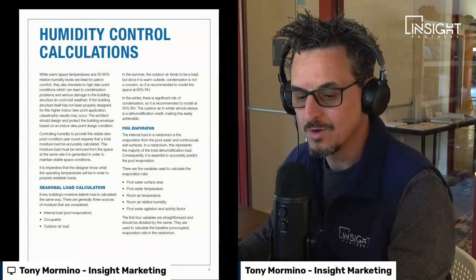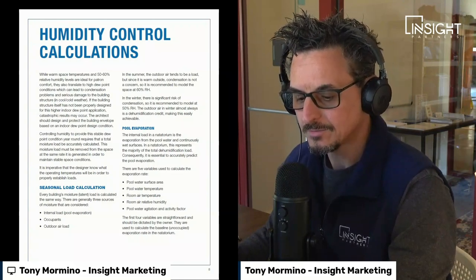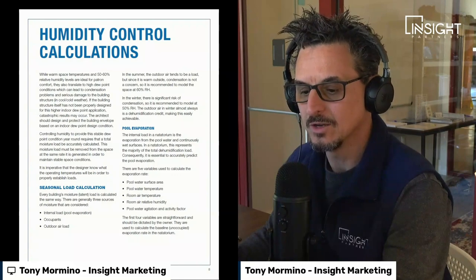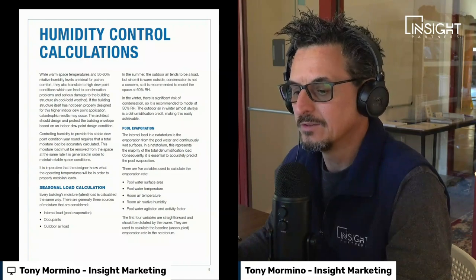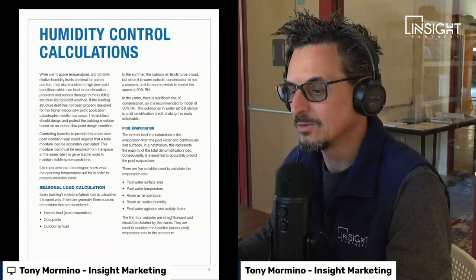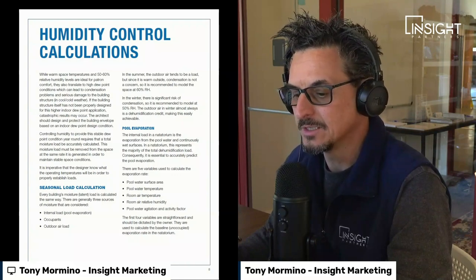It is imperative that the designer know what the operating temperatures will be in order to properly establish loads. There are generally three sources of moisture to consider: internal load (pool evaporation and occupants) and outdoor air load. In summer, the outdoor air tends to add moisture to the space, and since condensation is not a concern, it is recommended to model this space at 60% RH. In winter, there is significant risk of condensation, so it is recommended to model at 50% RH. The outdoor air in winter almost always provides a dehumidification credit, making this easily achievable.